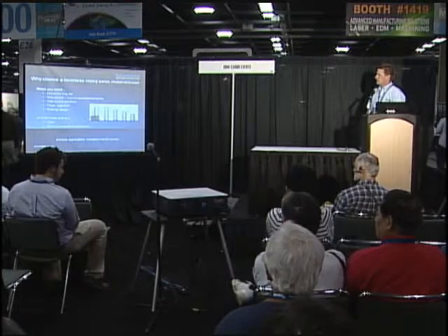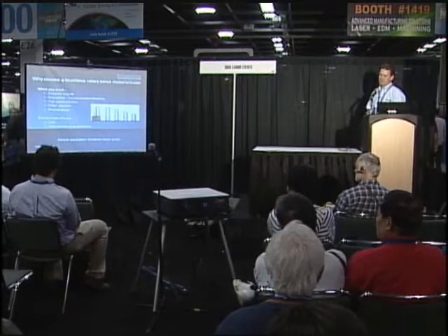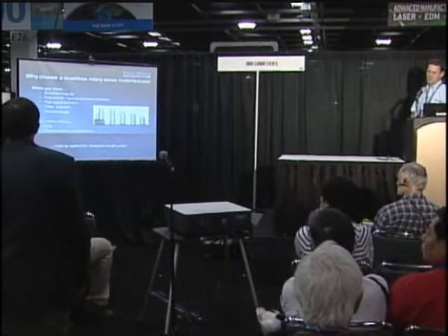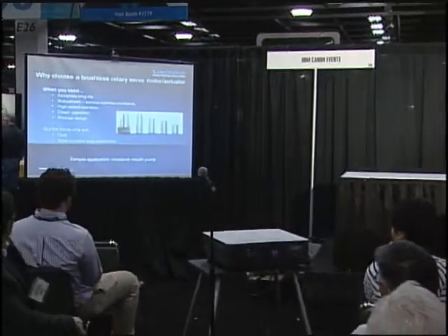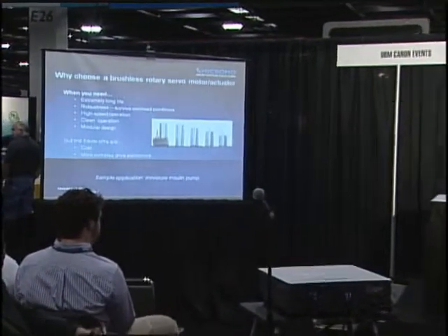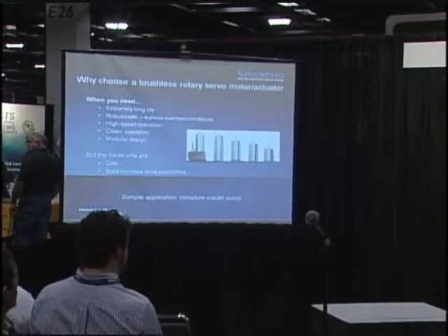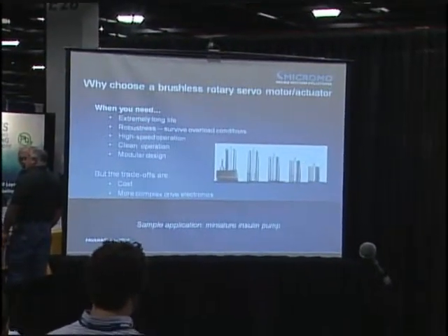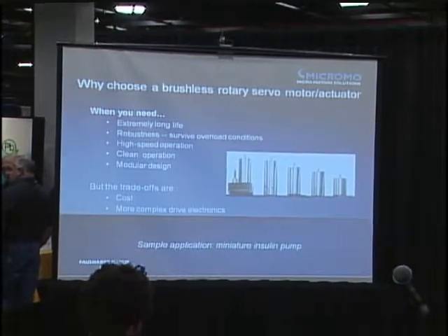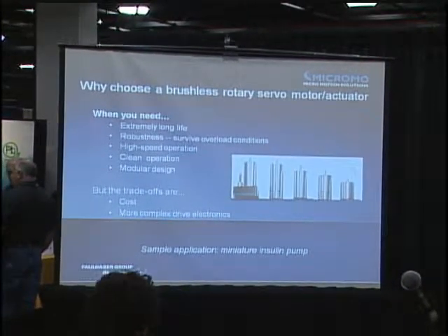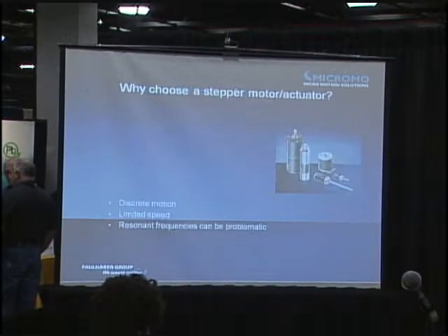And miniature insulin pumps are starting to use more brushless motors due to their robustness. Brush motors can tend to be kind of finicky in those small devices. You're talking maybe a 4 millimeter diameter motor. That's awful small.